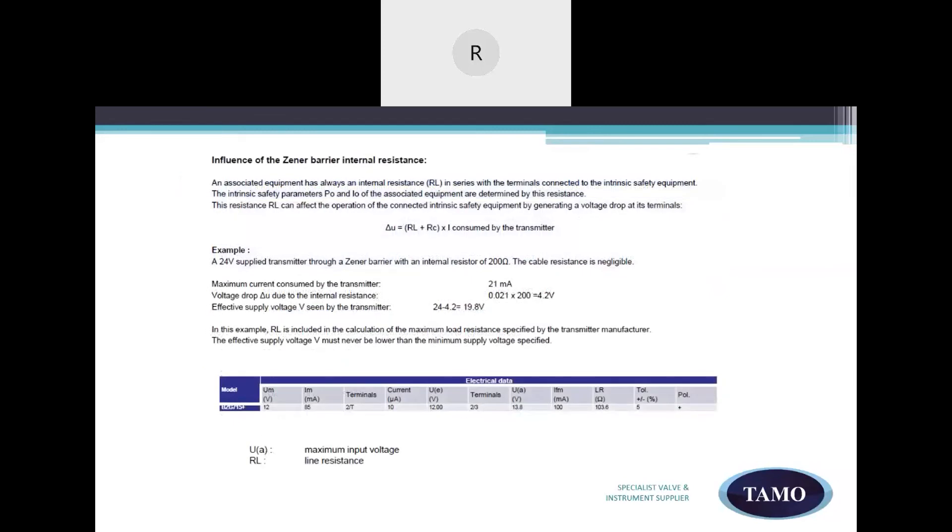The voltage drop across terminals. An associated equipment always has an internal resistance with the terminals connected to the intrinsically safe equipment. This resistance can affect the operation of the connected intrinsically safe equipment by generating a voltage drop at its terminals. So careful calculation must be done to ensure that there is sufficient power at the field device in the hazardous zone. The effective supply voltage must never be lower than the minimum supply voltage supplied by the manufacturer.